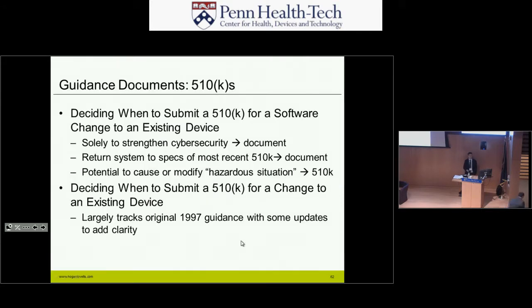So two guidance documents that actually just came out, I think 2 days ago, are deciding when to submit a 510K for a software change to an existing device and deciding when to submit a 510K for a change to an existing device. Basically, there are some low-level changes that you can make once you have a 510K clearance that you can, we call it, document to file. And so you document what your change was, but there was no risk associated with it, so you don't need to go back for an FDA clearance for the device again. This helps clarify when you have a software change, what's going to be required for going back to FDA.